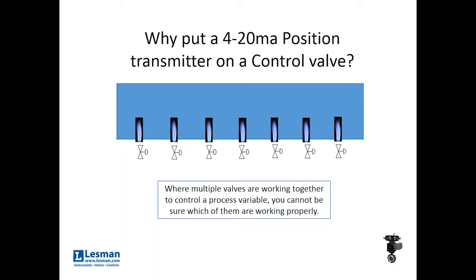Your controlled variable in this instance is the temperature inside that blue box. The control system's job is to bring that blue box up to temperature by turning a series of valves that are all basically getting a 4-20 from the control system. The problem in this environment is the control system has no way to understand if valve number two doesn't do its job.